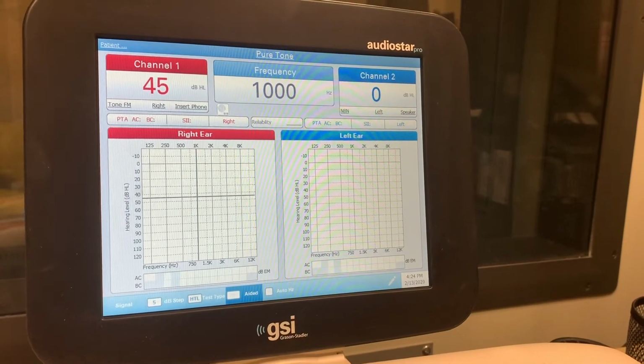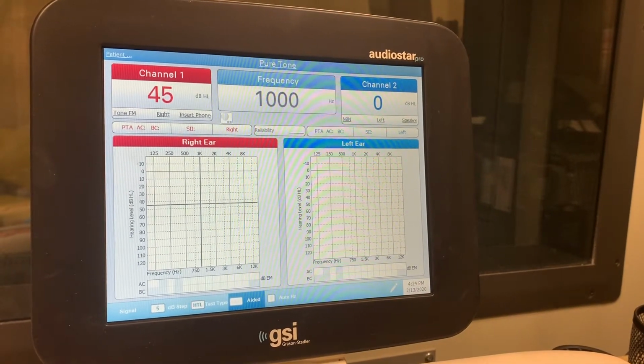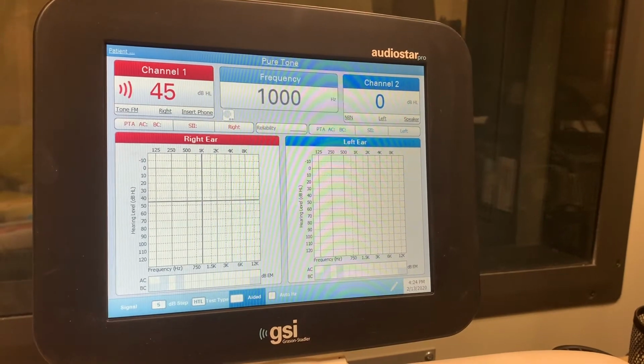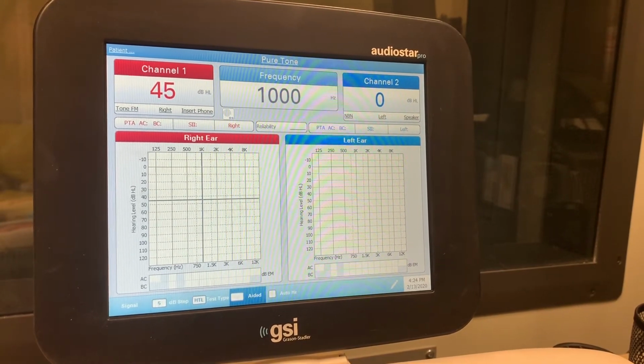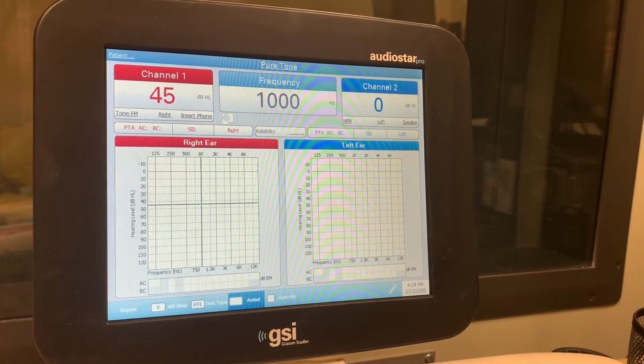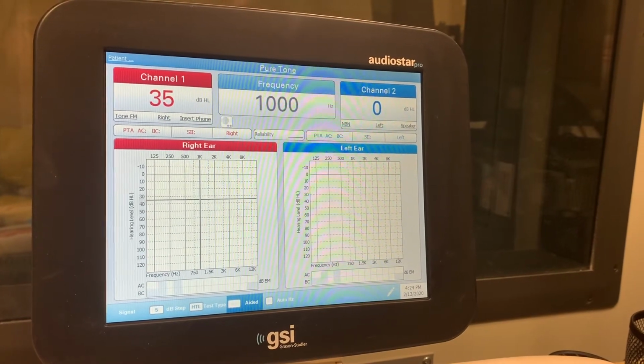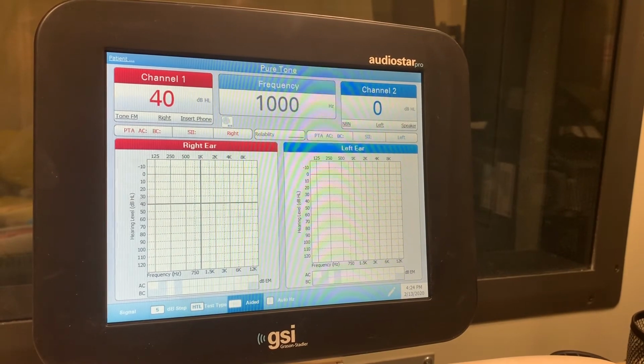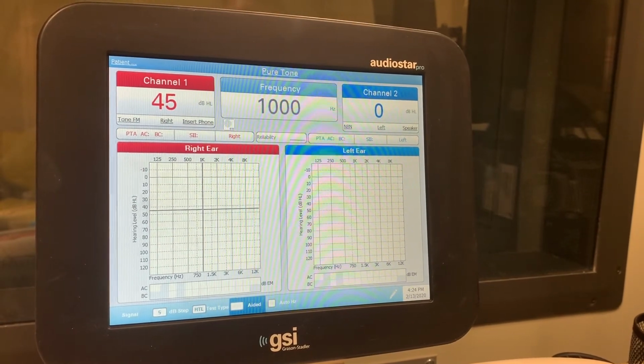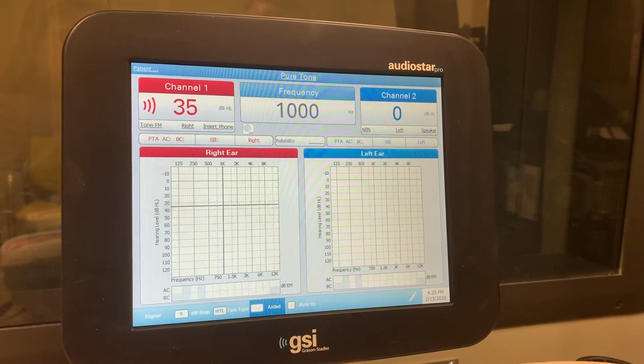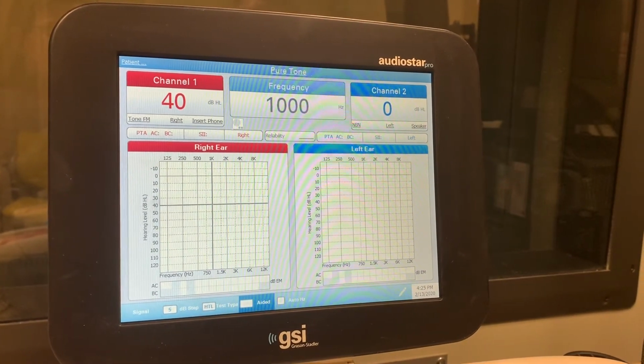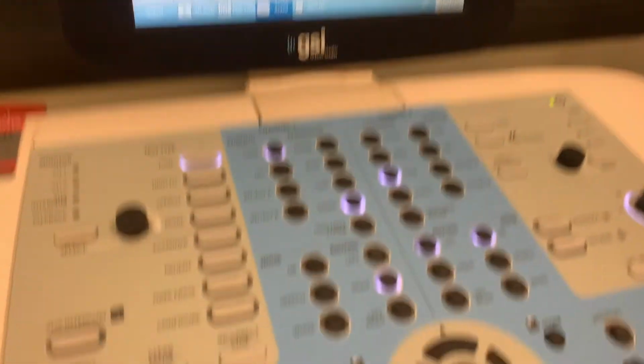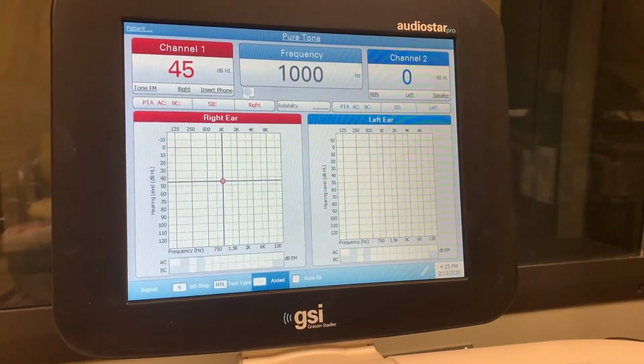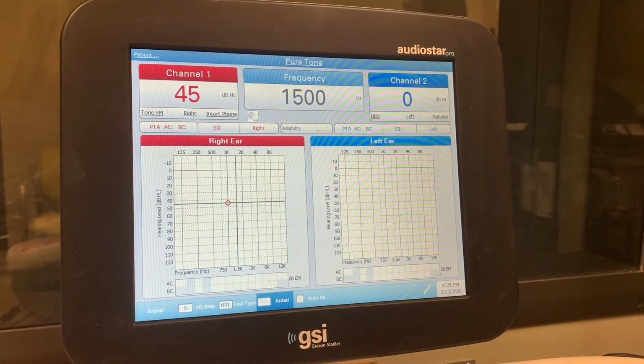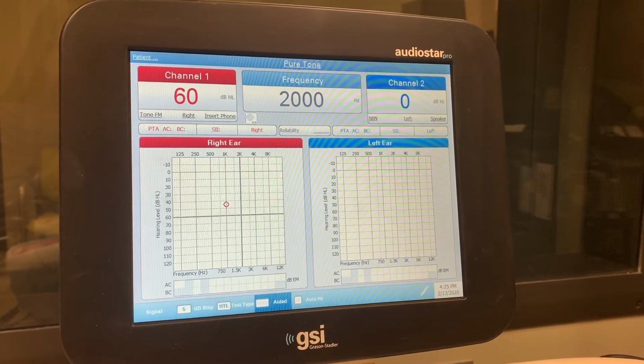So with this audiometer, you'll do your same best practice of presenting. If you have another audiogram to compare to, you can use that to help guide you, but you drop down 10. If they don't respond, you keep ascending until you achieve 2 threshold responses. And then once you get to that point where they give you 2 responses, you can hit the store button, which will then mark the response on the audiometer. And then you continue forward, getting all of the responses that you need.